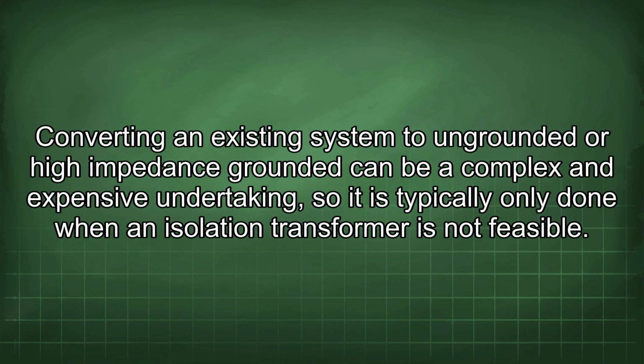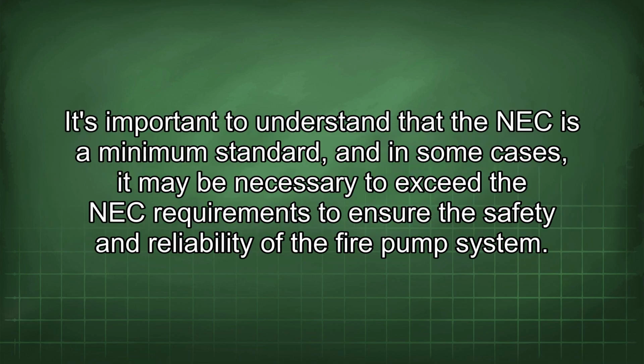Converting an existing system to ungrounded or high impedance grounded can be a complex and expensive undertaking, so it is typically only done when an isolation transformer is not feasible. It's important to understand that the NEC is a minimum standard, and in some cases, it may be necessary to exceed the NEC requirements to ensure the safety and reliability of the fire pump system.